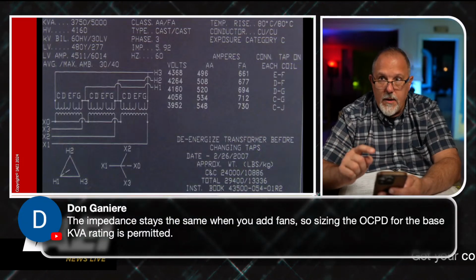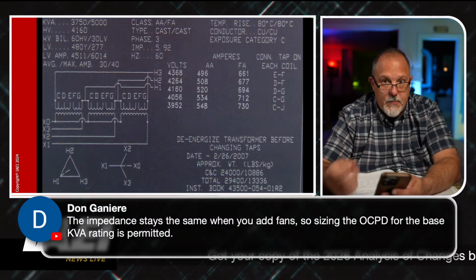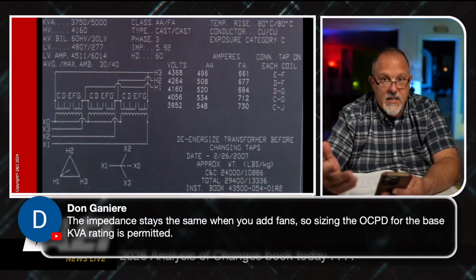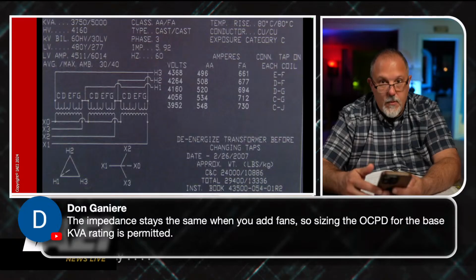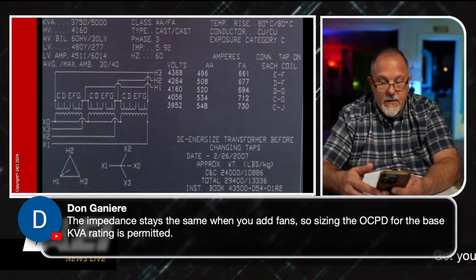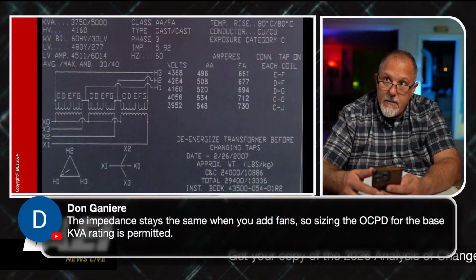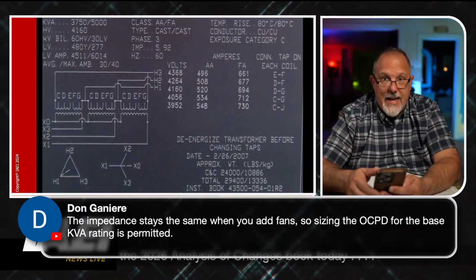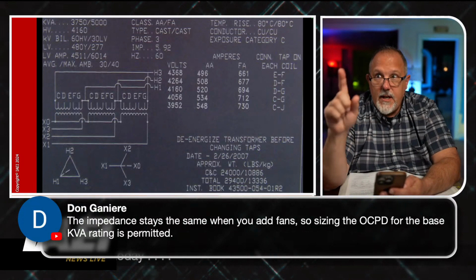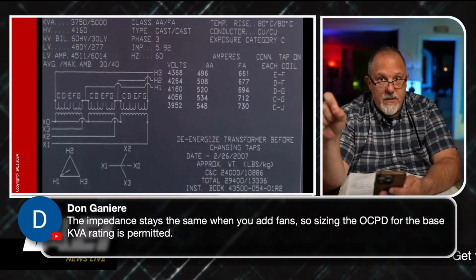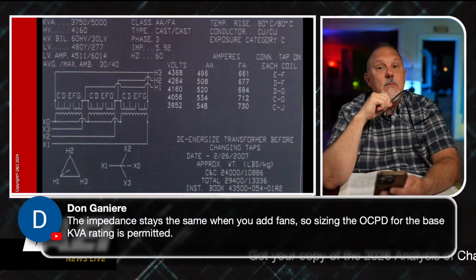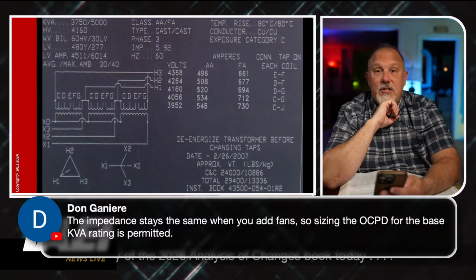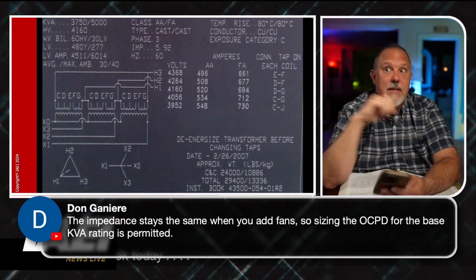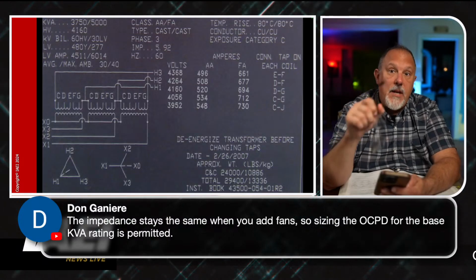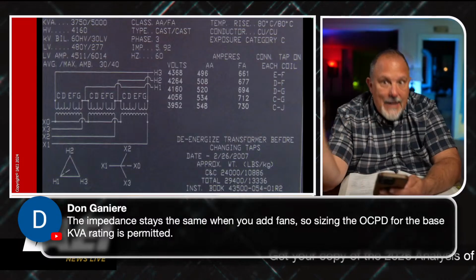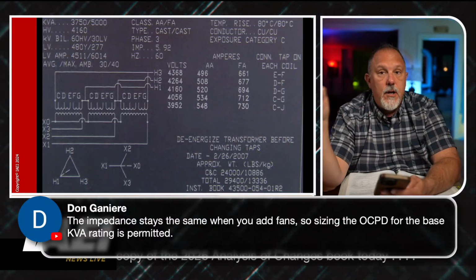Don, I may not have to worry about it on the primary, but on the secondary, I can pull more load, and I could supply more load from this transformer. So picking my maximum size overcurrent device would be impacted based upon the kVA and the fans added, because my overload protection is on the secondary. But what if I have future fans? I can't size my secondary overload protection based upon future fans at the 5,000 kVA because I don't have the fans on there. So I would have to be mindful of that and make sure I use the lower kVA unless I added those fans, because the fans are there for the overload of that transformer.